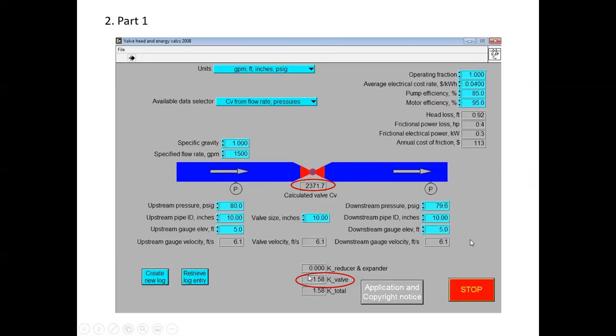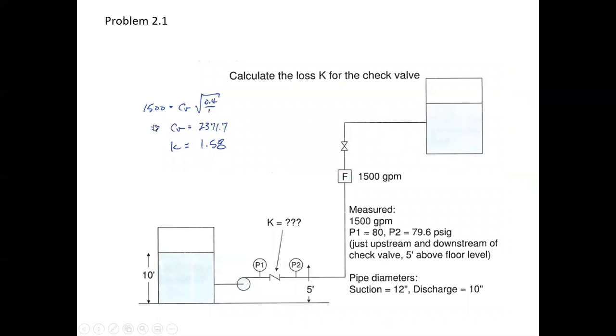It gives me the K value, and it knows there are no reducers or expanders because I have 10 inch, 10 inch, and 10 inch, so those get zeroed out. And so I have the K for the valve, which is the total K from this pressure to this pressure. Okay, so 1.58 is my answer.